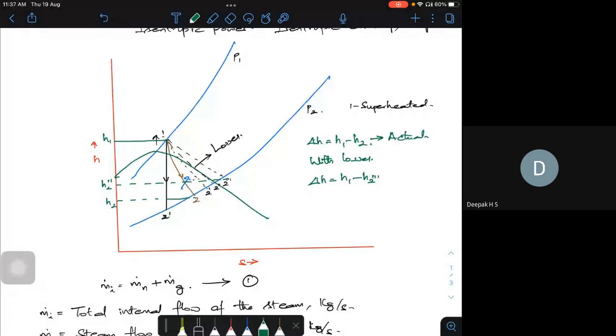So this keeps increasing. There are losses due to friction, losses due to the blade not being properly fixed, losses in the moving blade, losses in the nozzle, a lot of things. If there is an escape of steam through the gaps, those are leakage losses. All these factors will lead to a drop in your shaft power, or the work done by expansion.